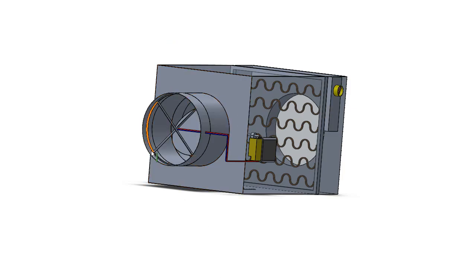On the backside, looking in through the inlet here, you can see these tubes which are coming from the controller and entering into there and connecting to this weird cross shape. This is an air flow sensor. And it is basically measuring the change in pressure across this device. And from that, you can average this and calculate the air velocity or flow rate into the VAV box.